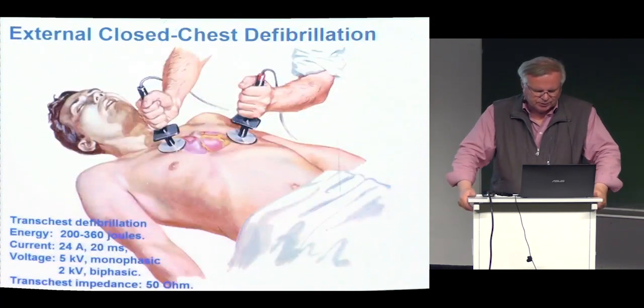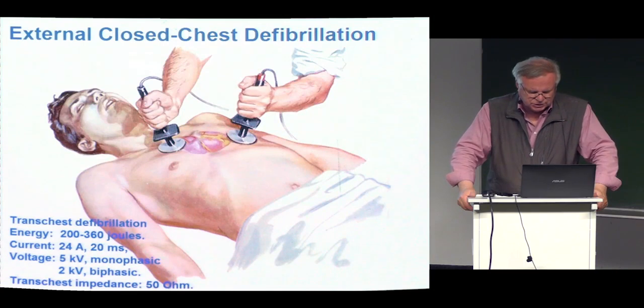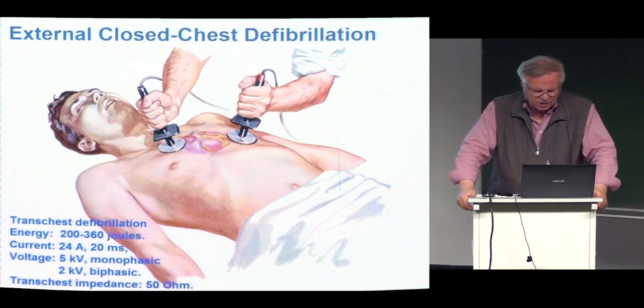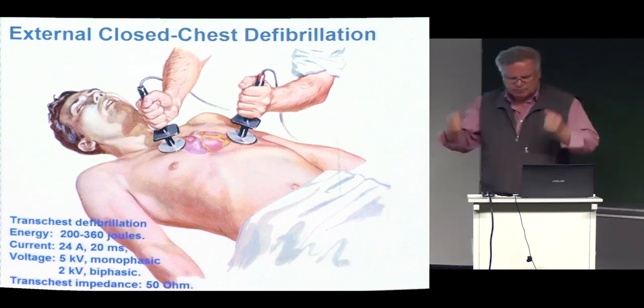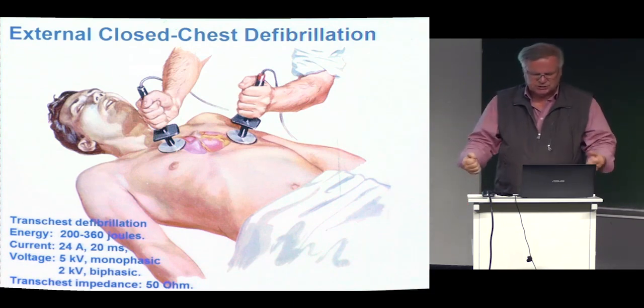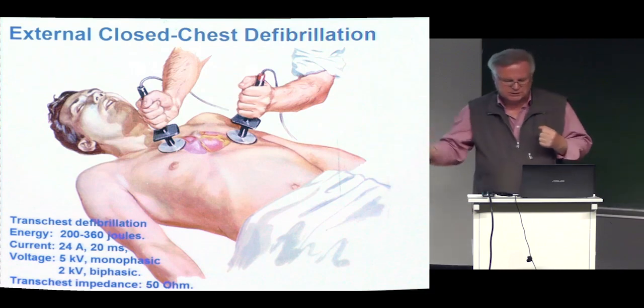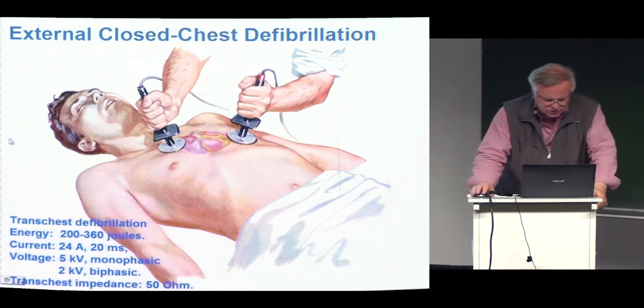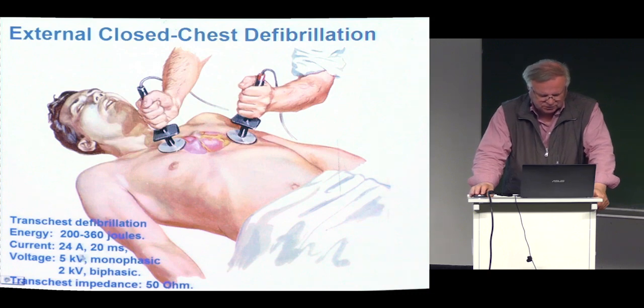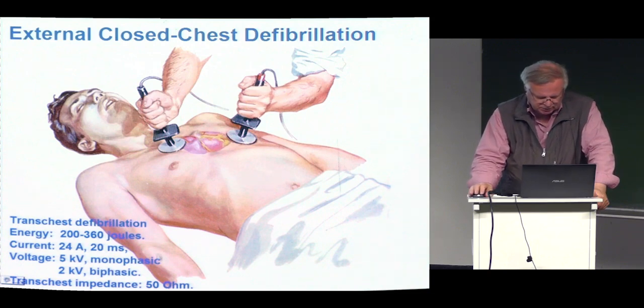Here it is shown how external closed chest defibrillation is performed. The defibrillation electrodes are placed on the chest so that the current passes through the heart. In trans-chest defibrillation, the energy is about 200 to 360 joules, the current is 24 amperes for about 20 milliseconds, and the voltage is 5 kilovolts in monophasic and 2 kilovolts in biphasic stimulation. The impedance between the electrodes is about 50 ohms — it's a very strong pulse.